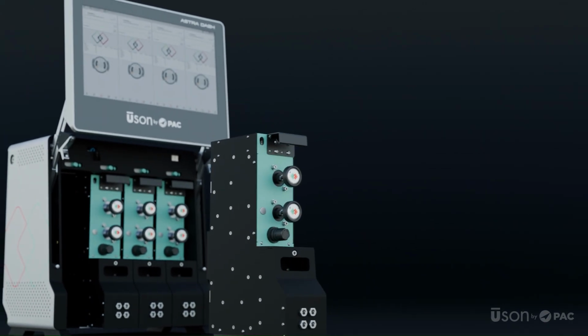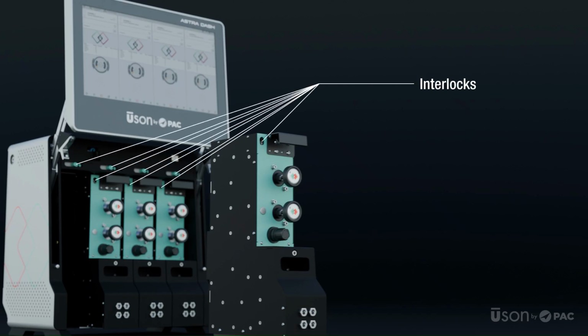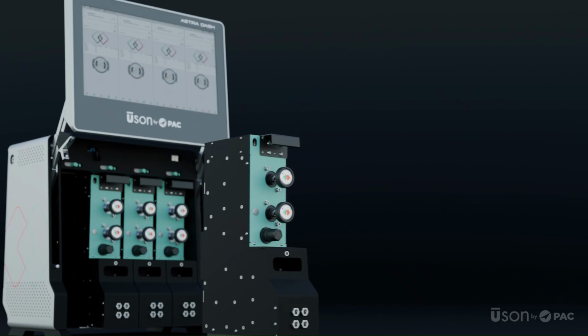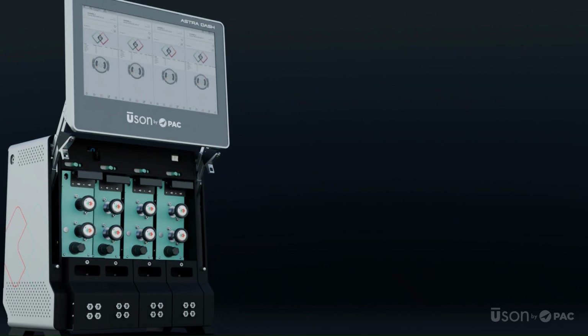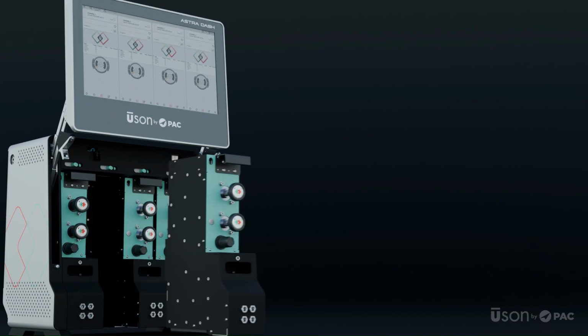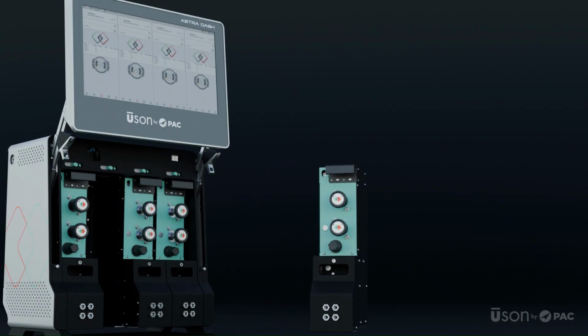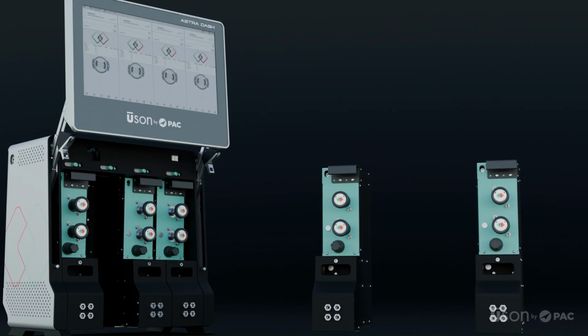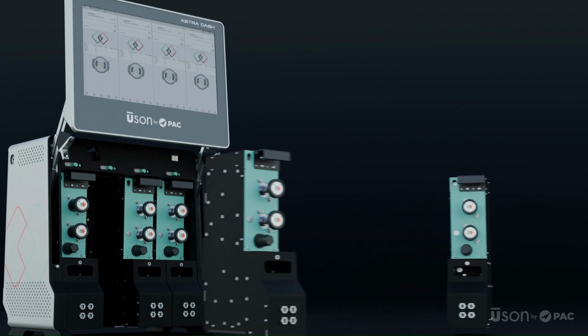Docking and undocking can be performed in 3 simple steps, with safety interlocks to control order of operations, and affirmative power and data connections are maintained by a captive drawbar. The channel box can be exchanged in minutes with a spare to return a channel to operation whenever service or calibration is needed, or can be swapped with one configured for a different test method enabling flexible operations. This innovation is perfect for customers who want to test a different product on demand with the same instrument.